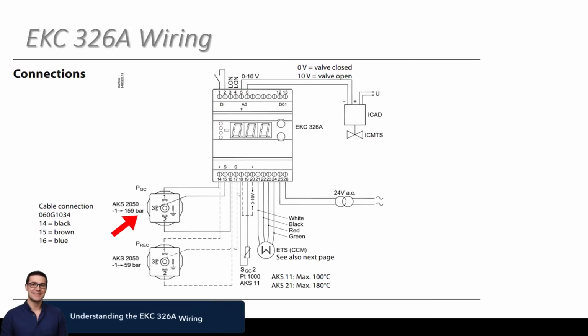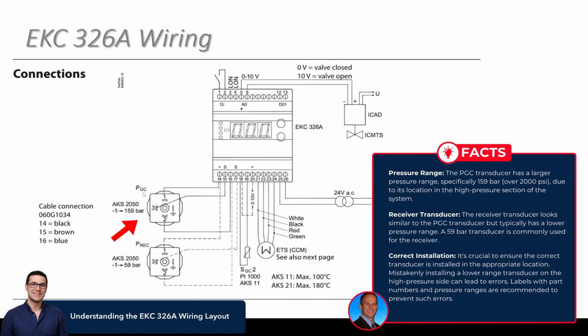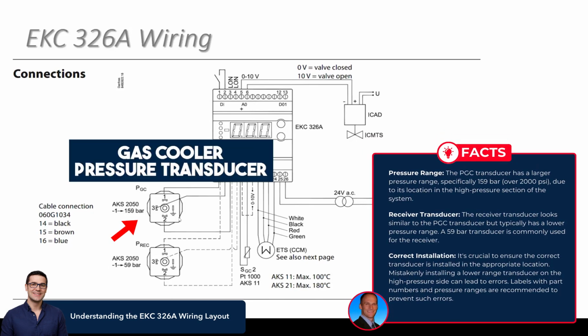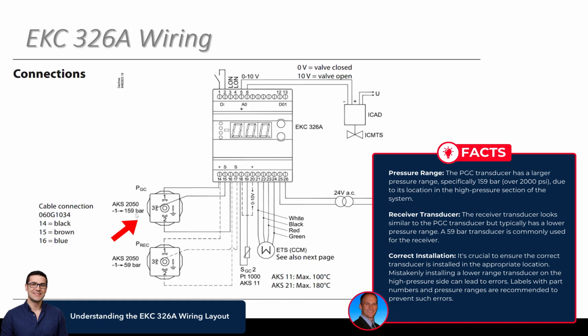On the lower end of the controller now, again, the 2 pressure transducers we have. So PGC, and we love our acronyms and abbreviations, and these are consistent is one of the good things. So abbreviation you see here on the 326 would be the same with our pack controllers as well. But PGC, our gas cooler pressure transducer, this is at the outlet of the gas cooler for our high pressure valve mainly. And this does have to be a bigger range. So this is a 159 bar or just over 2000 PSI range on this transducer.